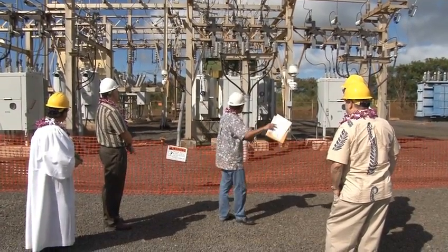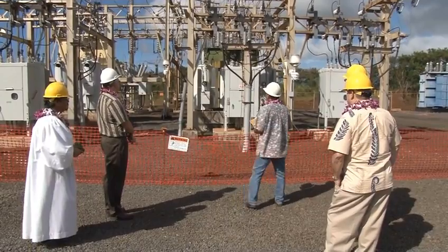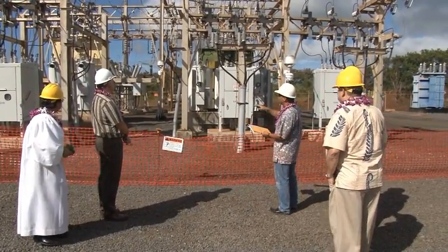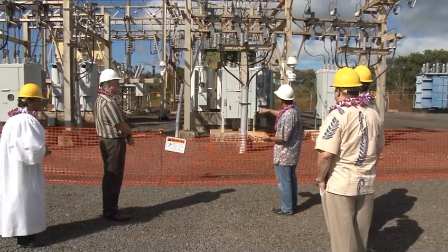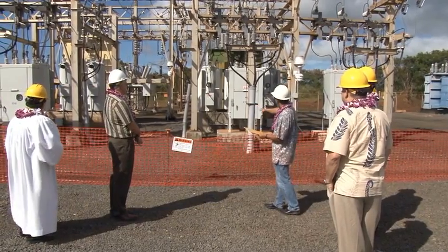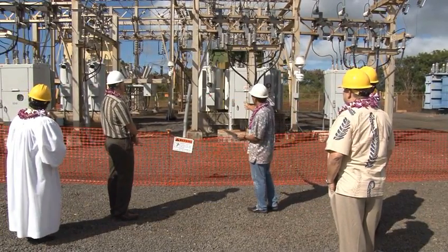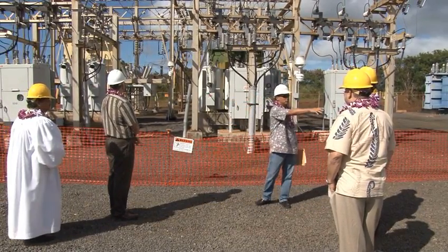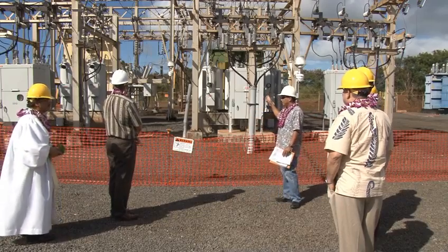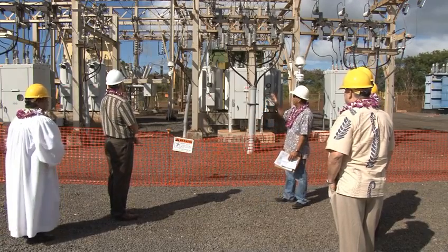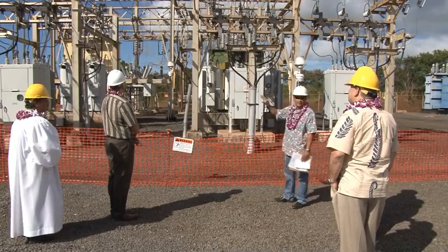So how this battery is tied in here: we have four feeders that spread out through the island, but you see the two feeders right on the side of the bus here, they're brand new. Those are actually coming into the switch gear over here. So this battery and PV is actually powering one side of the bus at any given time.